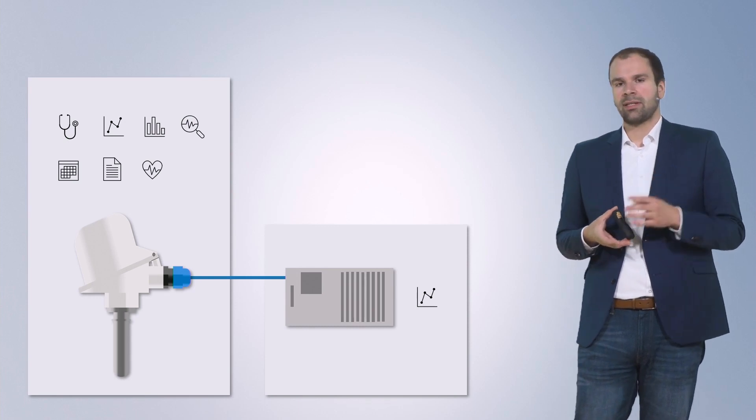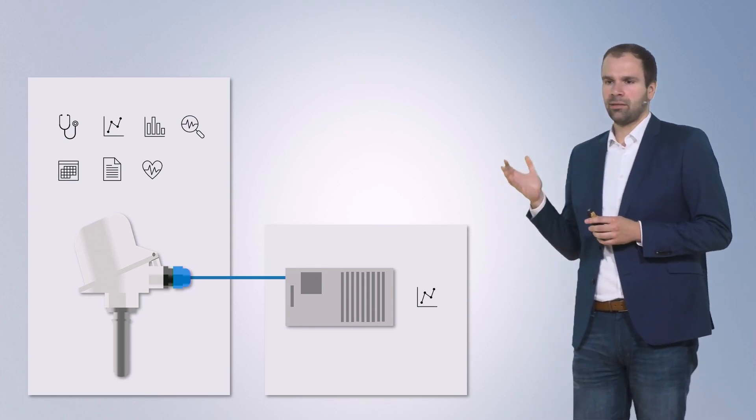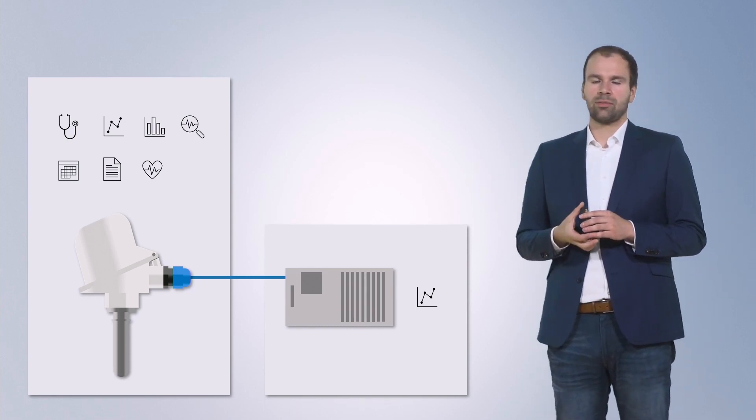For example, here we have a smart field device — a temperature sensor — that already provides a lot of data. Typically, only the process value, in this case the temperature, is read from the device and used by the DCS system for process control. But there is a lot of other information the device provides, for example about the condition of the device itself, or about process quality. That kind of information is already lost on this first step.